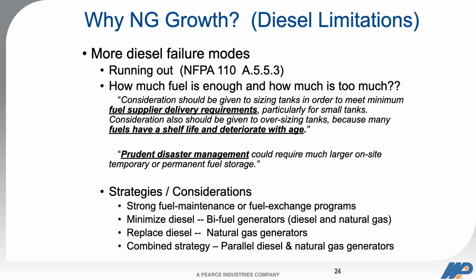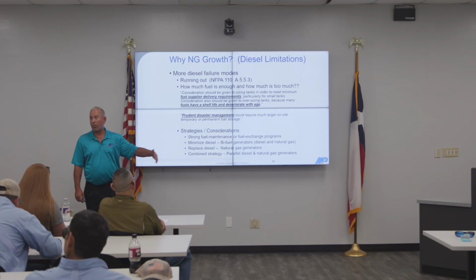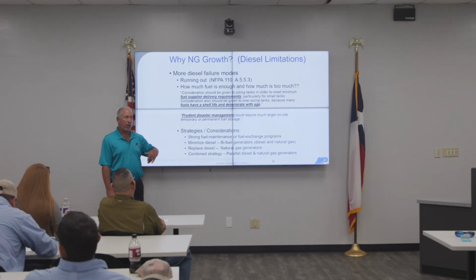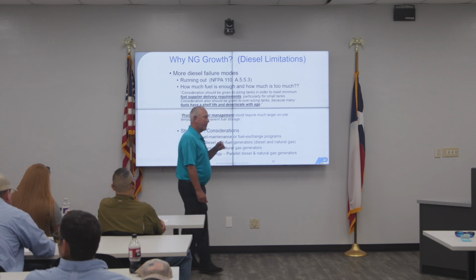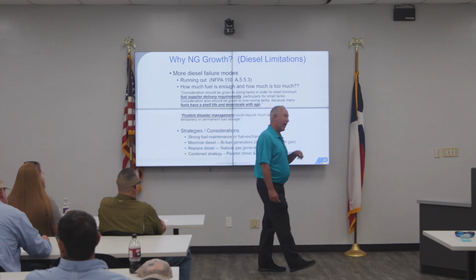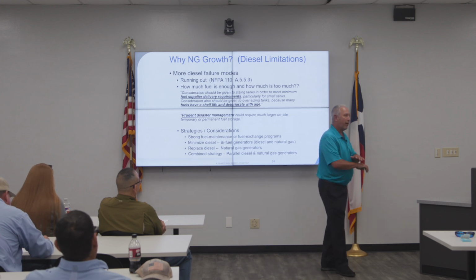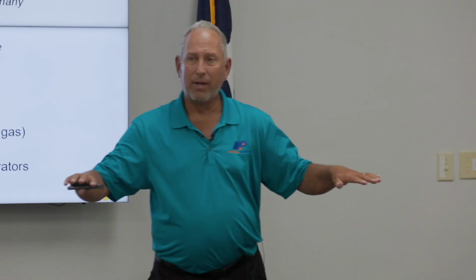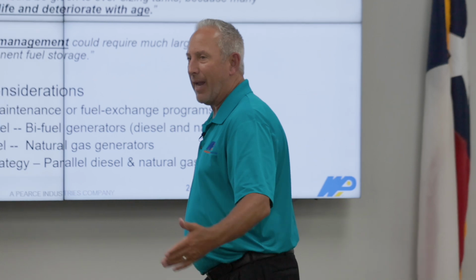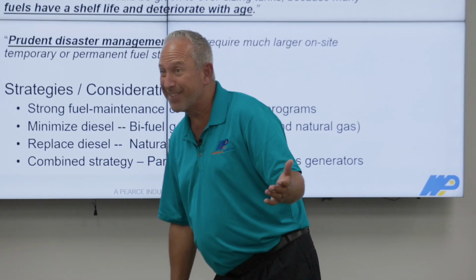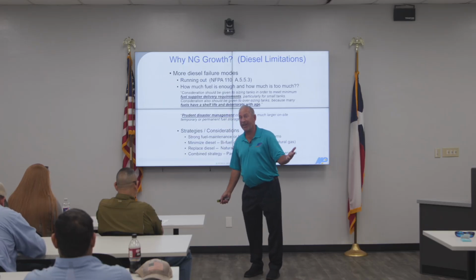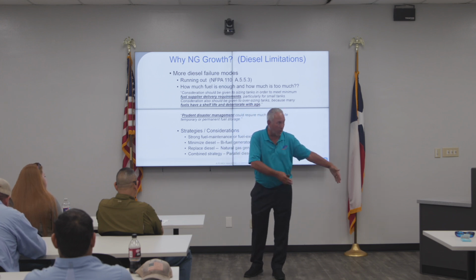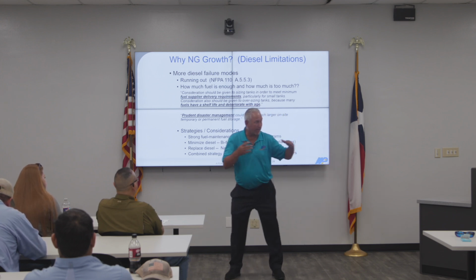There are regulations that dictate that. A lot of hospitals are 24 hours; 24, 48 is common. Every hospital has to have a 48-hour plan for an outage by law, or a 96-hour plan. So their plan may be that at hour 30 we leave—that could be their plan. They've got a requirement for local code to run, but they have to have a plan.